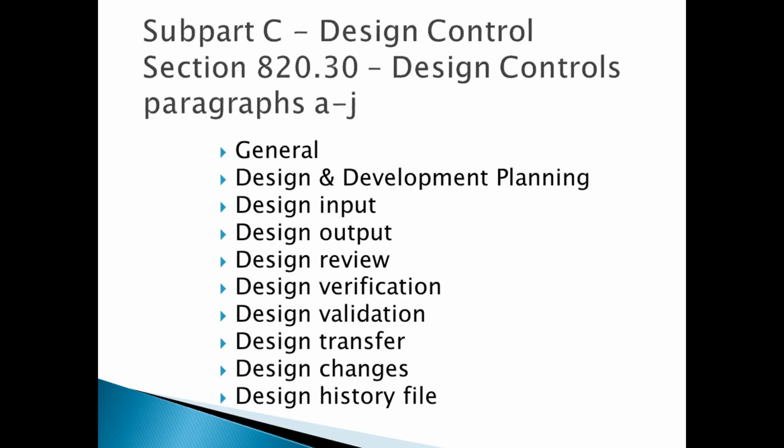And that's actually good because it allows each entity to come up with their own standard operating procedures depending on the types of products they develop and the types of customers that they're servicing. So we get involved with general provisions. We have the students develop a design and development plan. Design input consists of their design requirements. Design output are the specifications and prototypes. We conduct a series of design reviews, and it's interesting that these design reviews are important milestones for the students, and they get graded on this.